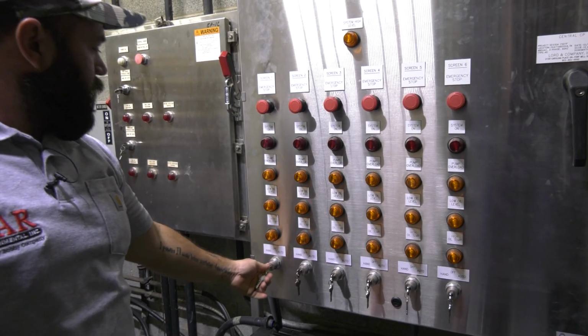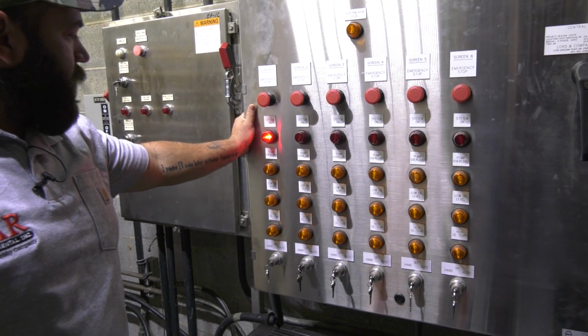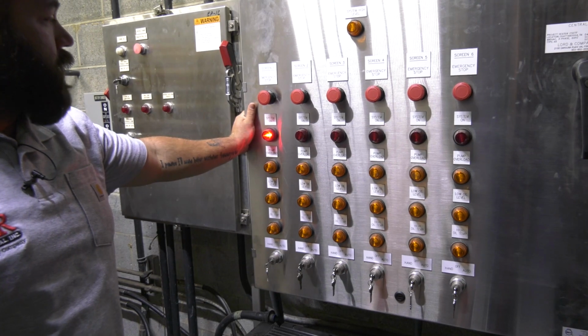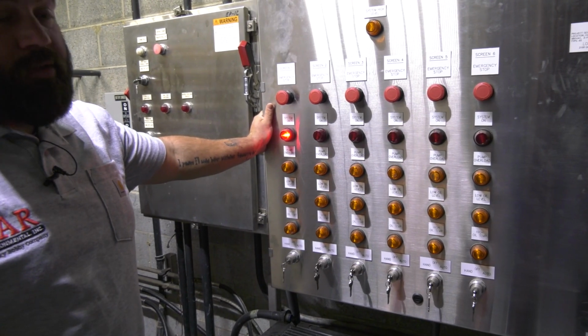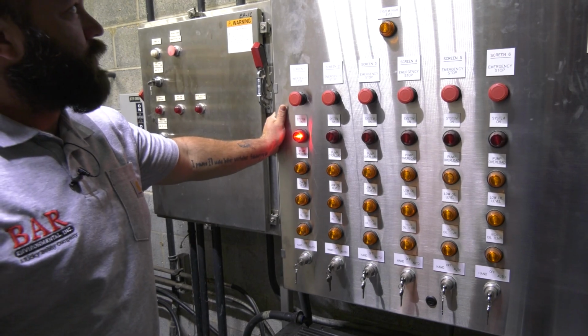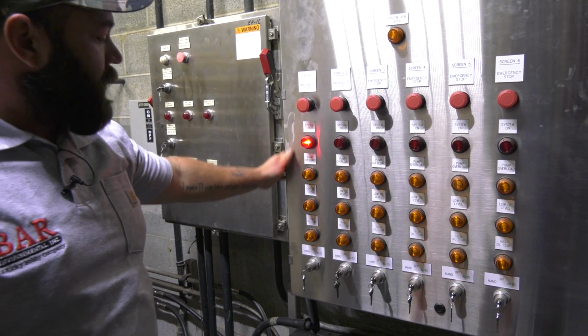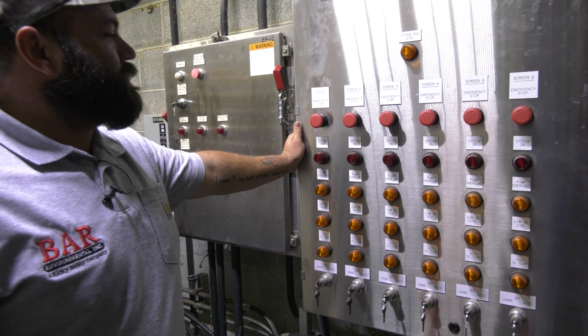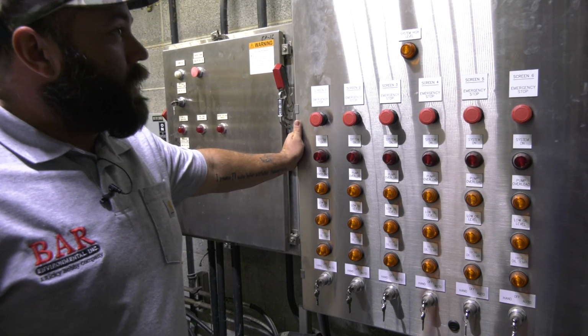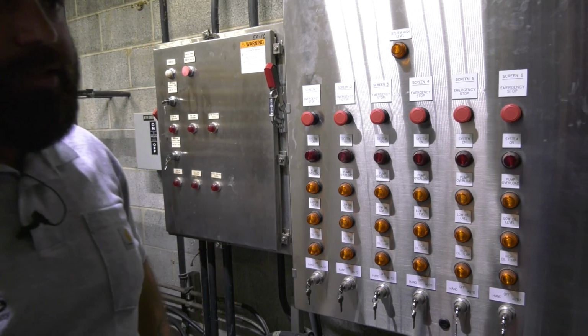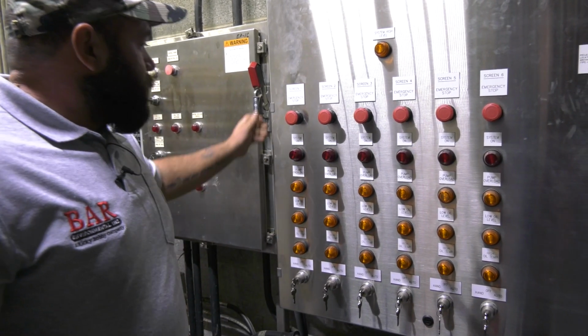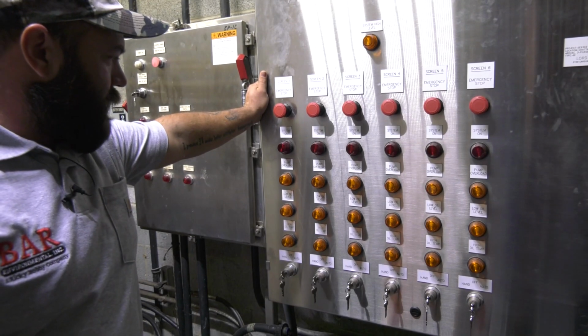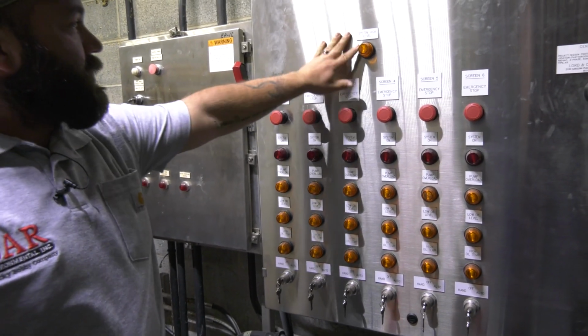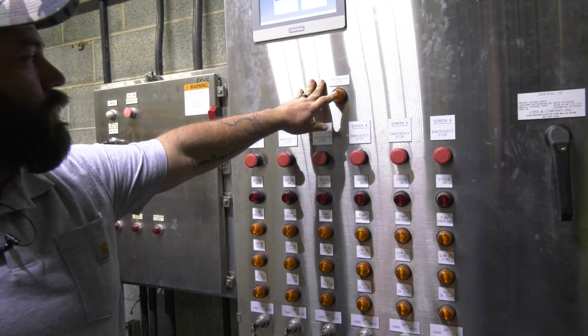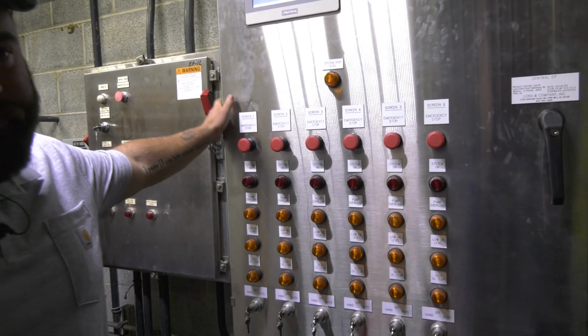So you can run these in hand mode, or you can run them in auto. Hand mode lets you manually run them. Auto is going to kick on as it sees the floats downstairs go from the low level to the high level, at which point the system is going to actively engage. That's pretty much all I got on this. System high level, what is that telling us? The system high level means you're past the low level float and you're at the high level. So the system high level right here is your high level float engaged, and it means the system's operational.